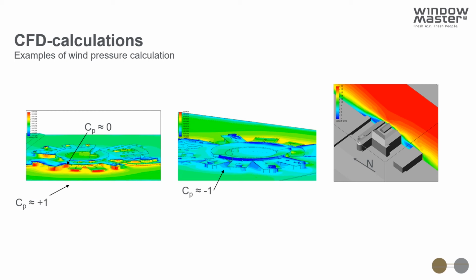You can see the different rooms and spaces and the different wind pressure coefficients around the building there. Essentially, if there's a demand for ventilation because of air quality or temperature deviating from or approaching the set points, we go to the weather station to see which direction the wind is coming from, how fast it is, and the outdoor temperature, then use the data file to look up the wind pressure coefficient on the vents in that space.